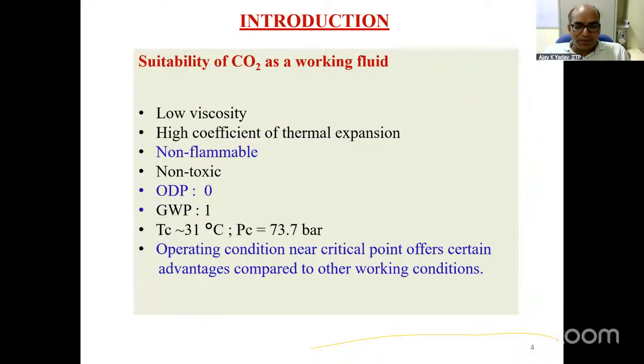Another point: ozone depletion potential, ODP, is zero. Compare this with other synthetic refrigerants like chlorofluorocarbons, which have very high ODP and GWP. Take R134A for example, its GWP is around 1300-1400, and ODP is 0. But R22 and R12 do have ozone depletion potential. Here ODP is 0 and GWP is 1.